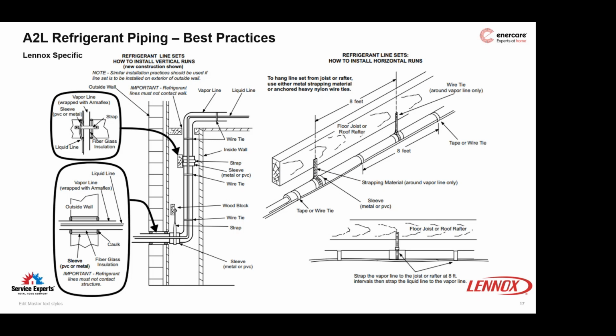The only reason I bring this up is I've had a couple instances where we've had to install a kit. Lennox has a kit that I had to install to stop a sympathetic harmonic that was vibrating through a piping system, one specifically in Fort Erie. I installed it around an elbow just before it went into the building, because the homeowner was getting a weird vibration and hum in their house. Once I put this kit on, it seemed to correct it, but I think the piping was strapped directly to the joist, and not hanging from it like this.